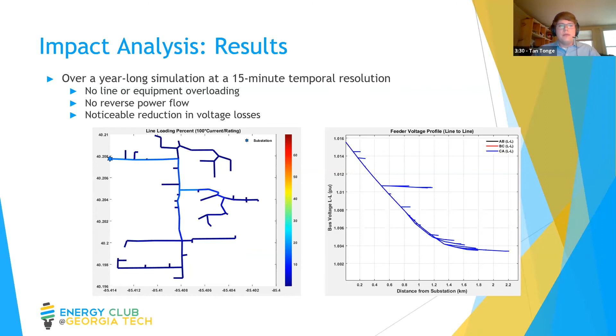I ran the simulation for a year, solving it every 15 minutes, and as we expected, there was no overloaded equipment or concerns for reverse power flow through the substation, and circuit voltage levels were slightly improved. These two graphs were generated at peak loading times, which were the biggest areas of concern. So from this data, I can confidently say the PV generation will not have any negative impacts on the distribution system, and it will be able to maintain proper operation.